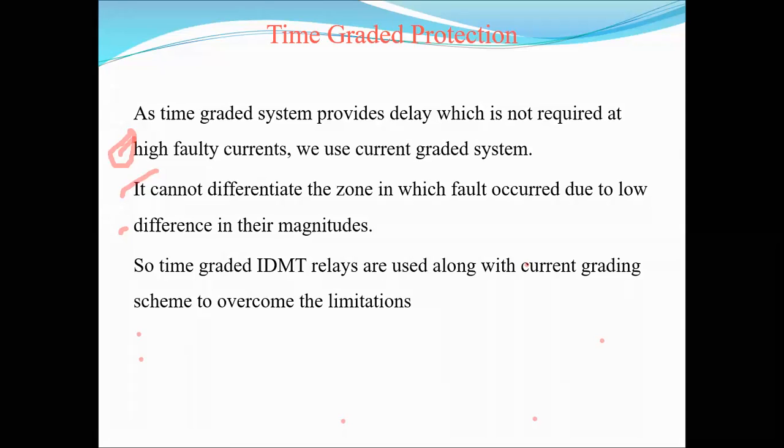In the previous slides we already discussed the time gradient protection. It is not suitable for high fault currents. It will be suitable only for low fault currents. That's why we are designing the current gradient protection. For small short circuit currents we use the time gradient protection. For large short circuit currents we use the current gradient protection. Based upon the current rating, that feeder line is operated.